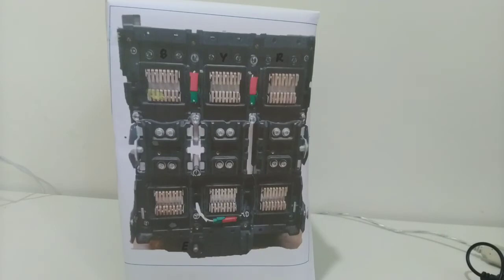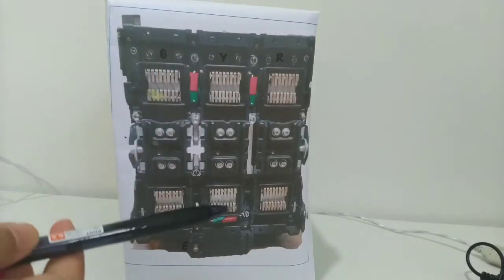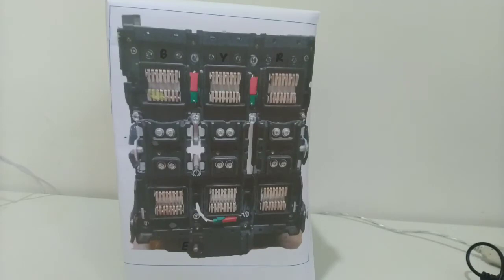Now, to do the open position, we need to discharge the testing point by connecting the wire to the ground terminal and touching the testing point. Just touch it repeatedly until it's discharged. Then, the same steps as the closed position, we now test for phase to phase and phase to earth.